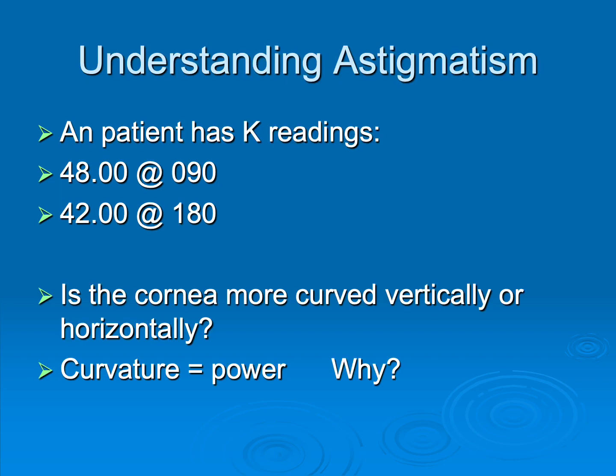For example: if you're measuring a radius of curvature of 7 millimeters, what is the refracting power of the cornea? In the formula, n' is the refractive index of the cornea (1.3375) — that's what we're entering. N is air (refractive index of 1) — what the light rays are leaving. We're dividing by the radius of curvature. When you work through it, you should get a value that looks like a K-reading, because a K-reading is the refractive power of the cornea. So now the keratometer has given us two values, and we ask: is this cornea more curved vertically or horizontally?